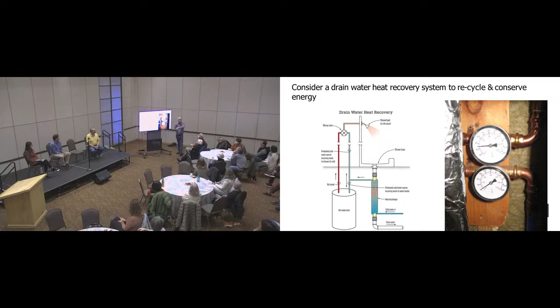These are gauges I put on ours. About 10 years ago in February, the water coming in from the city was 40 degrees. After it went through this device, it was up to almost 70 degrees. So it's preheating all that water and saving you a lot of BTUs.